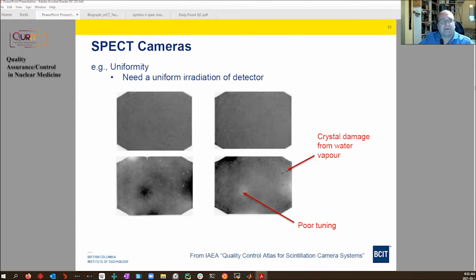So just to give you a sense of the uniformity, here's 4 images of rectangular field of view gamma cameras. For the top 2, a uniform irradiation was performed. We see that the image looks roughly uniform. Maybe there's something at the edges here. So if you were doing an acceptance test, you bought a new camera, you want to see something like this. There are quantitative numbers associated with this. You can quantify the uniformity. This is what you don't want to see visually.